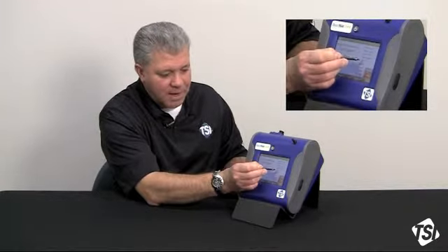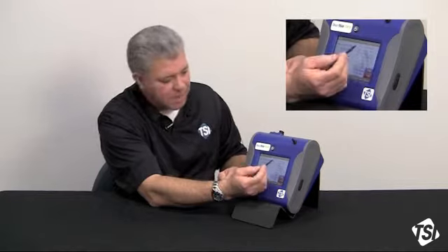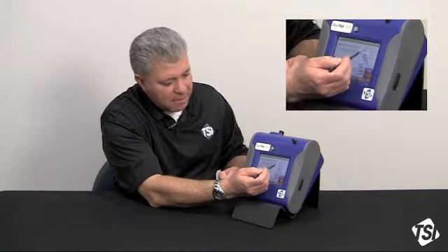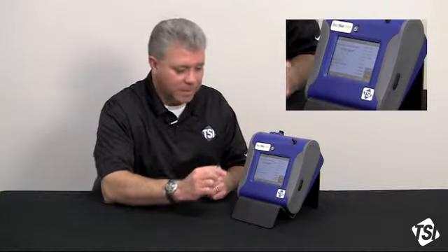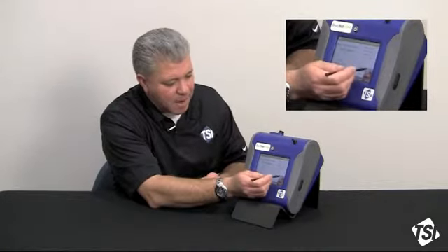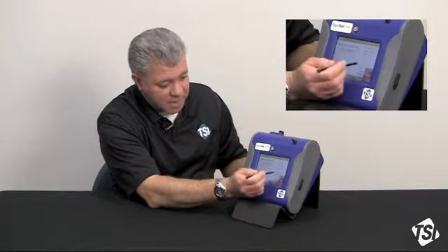Now, if I want to look for the stats associated with this sample, I push the stats button, and over on the right-hand side of the screen, my stats change. I have min, max, average, and time-weighted average data to look at during sampling. Very important to be able to look at data while you're taking a sample. Okay? If I touch the stats key again, I go back to having my regular concentrations displayed for all 5 size fractions.